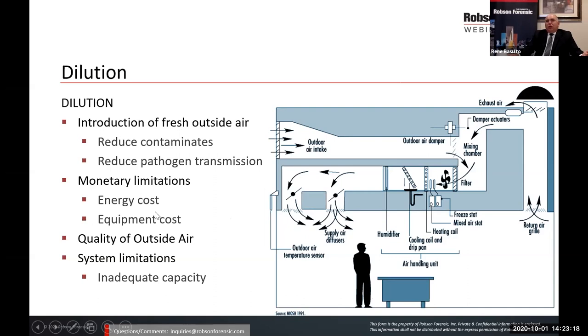First of all, the energy cost to treat this outdoor air, because aside from maybe a couple of days here in South Florida, we really can't bring in outdoor air without doing anything to it. And in most places throughout the country, you really can't bring in outdoor air when it's 30 degrees outside into the building without treating it somehow or heating it somehow. So we're doing that, but the cost of treating that air tends to be very high.